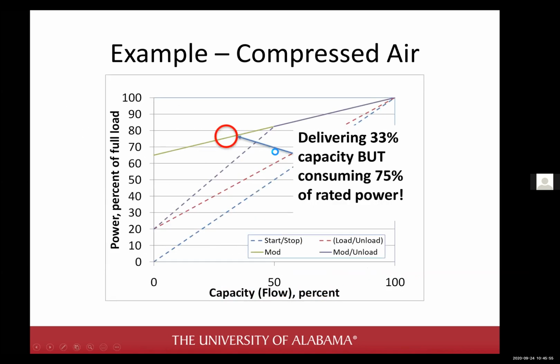Okay, so what is load unload strategy? Well, you set a pressure band. It's a lot like your thermostat, but you set a pressure band and the compressor goes on until it hits, for example, 110 PSI, then it shuts off till it goes down to 100, okay? And it goes on and off and on and off. It's not fully on-off because these larger compressors, you don't want to shut them down completely because it's really difficult to get them spinning back up again.